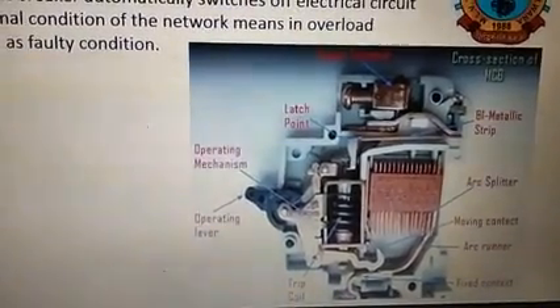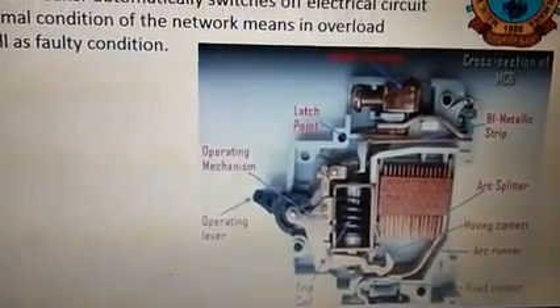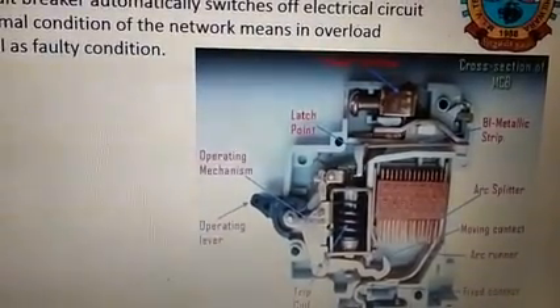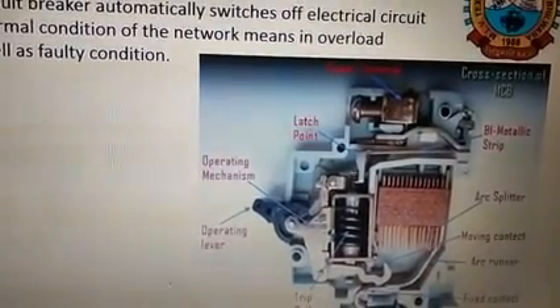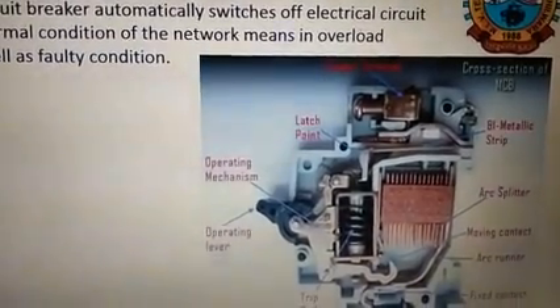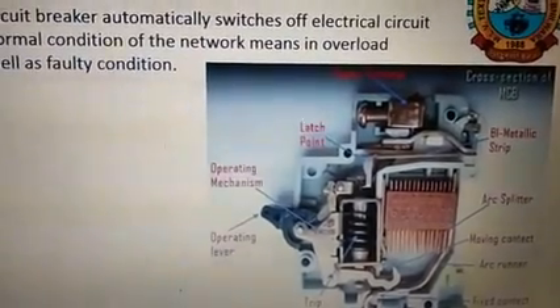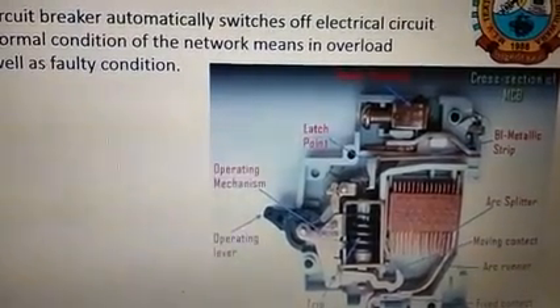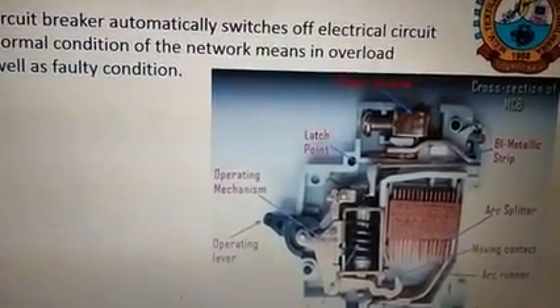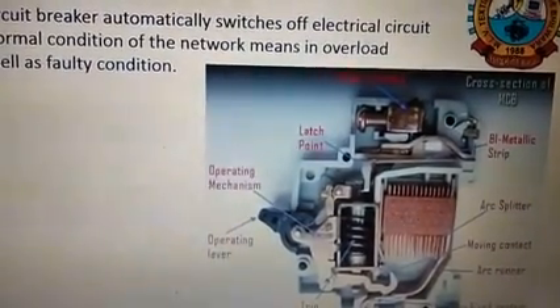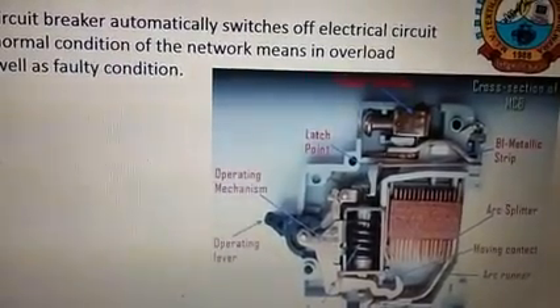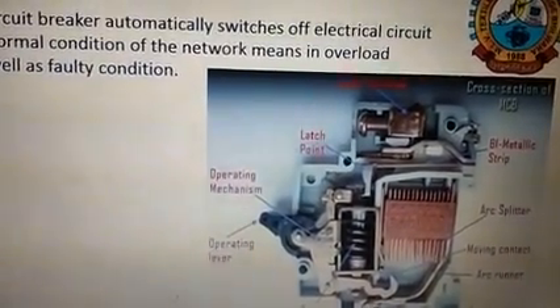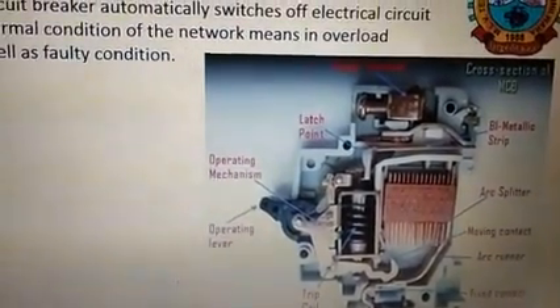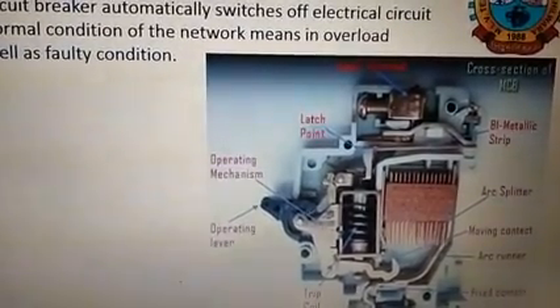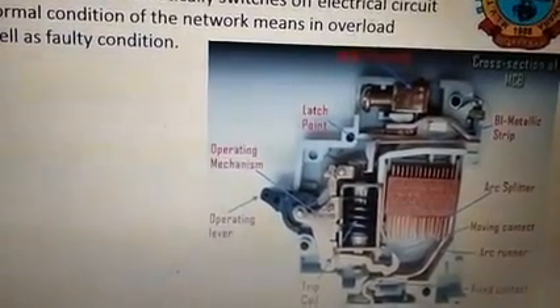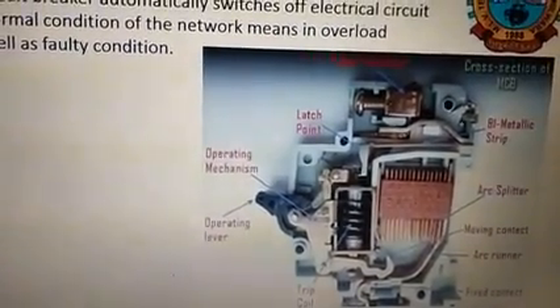At continuous overcurrent flow through the MCB, the bimetallic strip is heated and deflects by bending. This deflection of the bimetallic strip releases the mechanical latch. There is a latch point. As this mechanical latch is attached to the operating mechanism, it causes the miniature circuit breaker contacts to open, and the MCB turns off, thereby stopping the current from flowing in the circuit. To restart the flow of current, the MCB must be manually turned on.